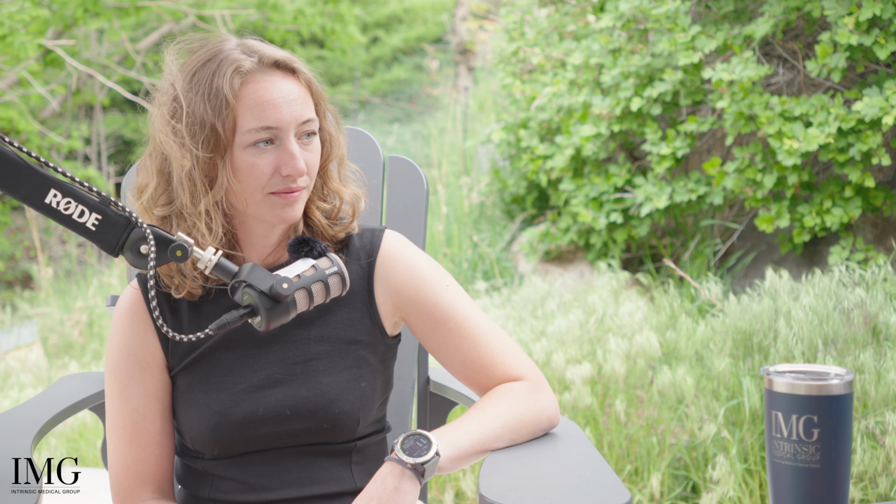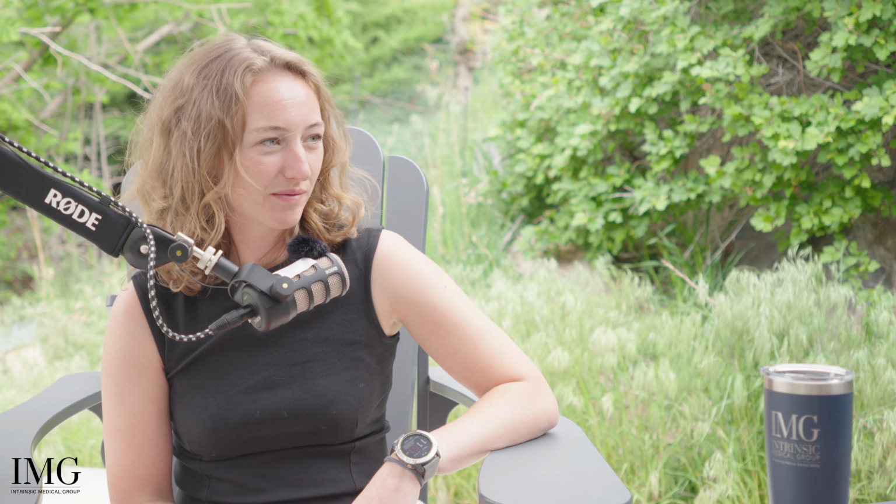Most implantation studies, I would recommend using a rabbit. And then if you need to go for bones, you can do rabbit, but sometimes it's better to go with a sheep. So like an orthopedic device, location will impact that a lot, as well as the life span of the animal and the duration of your study. So if you need something really long term, you're not going to be able to use a rabbit, because they won't live long enough. You need something that has a longer lifespan to be able to encompass that. So these are factors you start playing into.